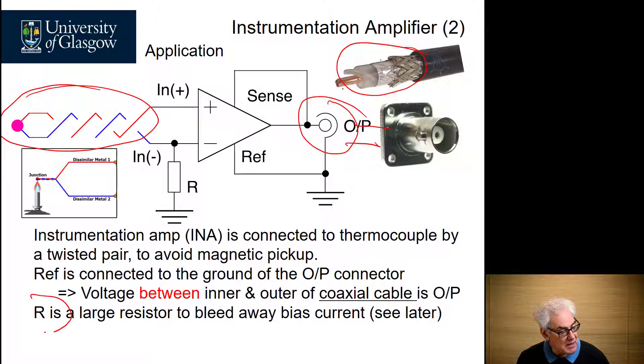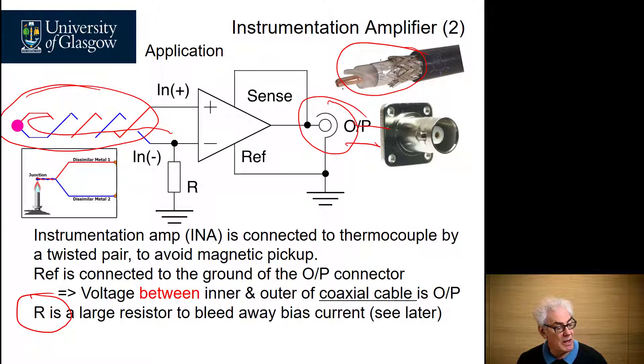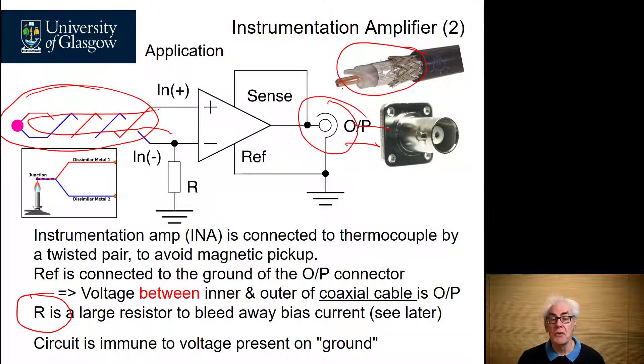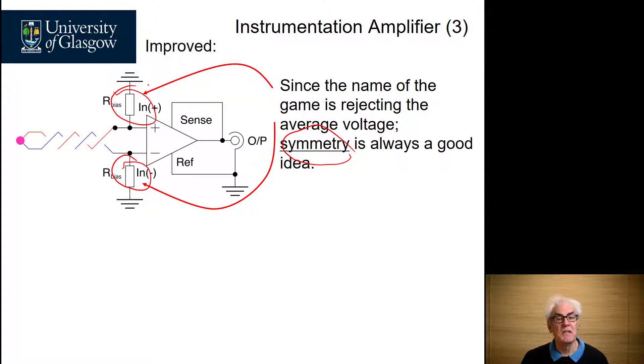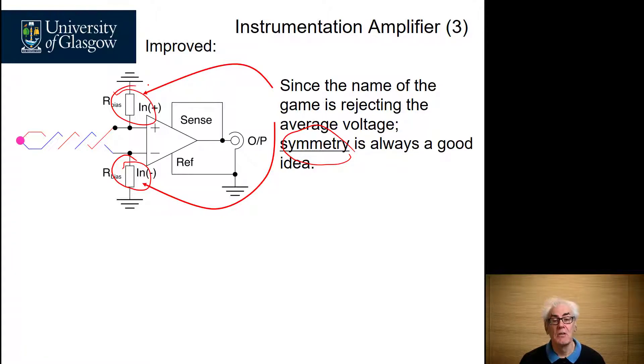In this instance, we've used a large value resistor just to supply or bleed away any bias currents required by the amplifier. And because a thermocouple has very low resistance through the wiring, the single resistor will actually provide the bias current for both inputs. The design of this circuit is pretty much immune to any voltage appearing on the ground signal, so it's only going to amplify the difference voltage. We can improve this slightly by improving the symmetry — incorporating two resistors to supply the bias currents to each input, which means that from a thermocouple and transducer standpoint, the input at both In(+) and In(-) looks identical from an electrical standpoint, and has a relatively high resistance to ground.